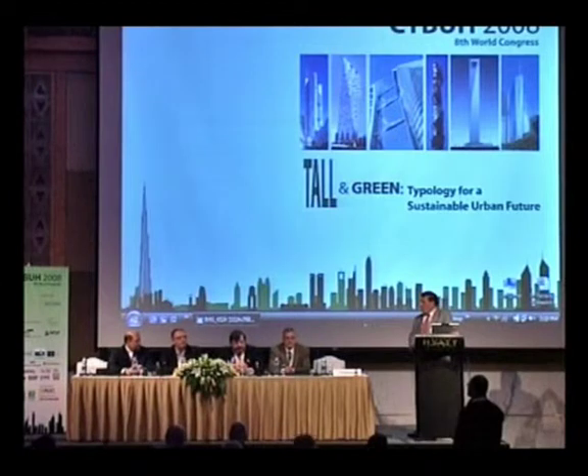So we can use pressurization, but we found as a design solution, perhaps it's to do with British construction techniques, I don't know, but it tends to work better if we use alternative solutions. It's just a bit more robust, because if we need to put a bit more air into these mechanically assisted systems, it's a relatively simple matter of making the fans slightly bigger. With a pressurization system, if it's not working, if you're getting big losses through the system, putting a bigger fan on isn't necessarily going to solve it, because you end up with diminishing returns.